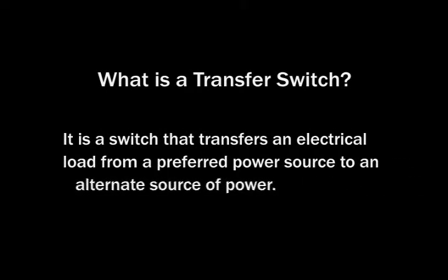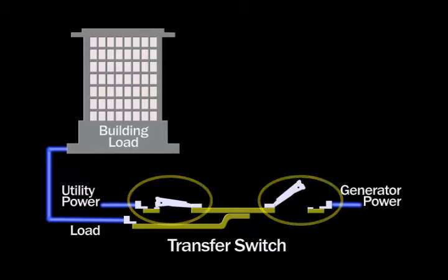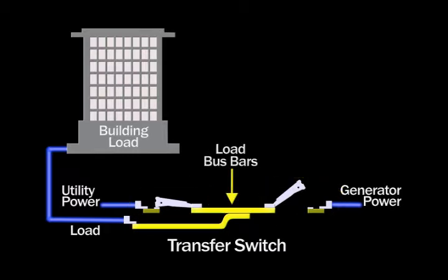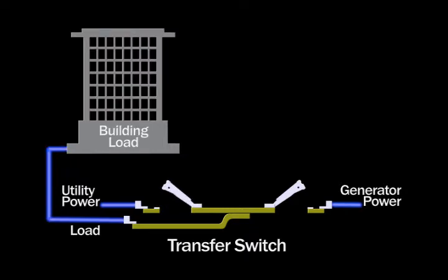A transfer switch is a switch that transfers an electrical load from a preferred power source to an alternate source of power. The load is usually switched from the utility company to an emergency generator. The transfer switch has two sets of electrical contacts, one for each power source, connected together by the load bus bars. The electrical load of the building is connected to the load bus terminals and can be switched to either power source manually or automatically.